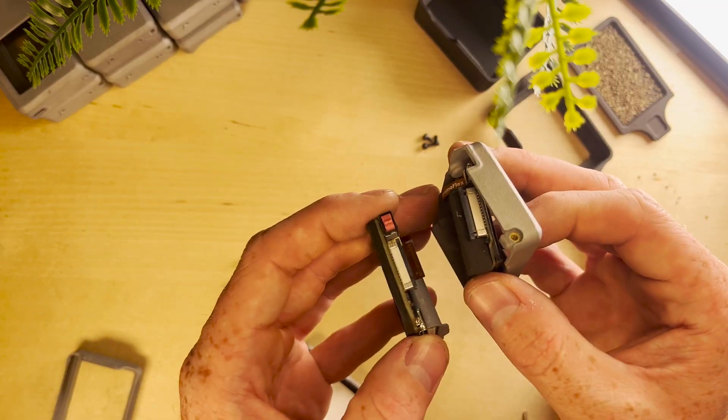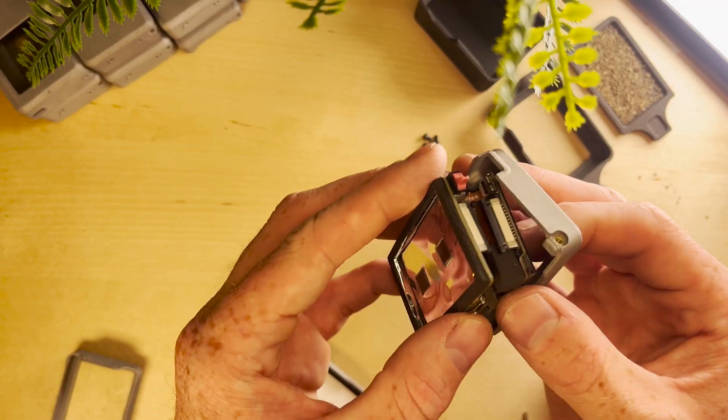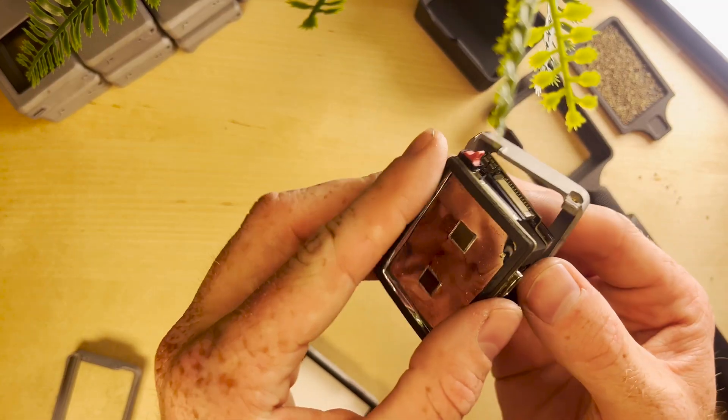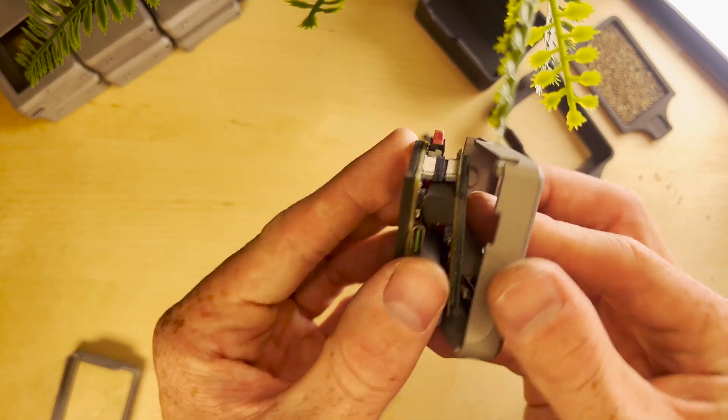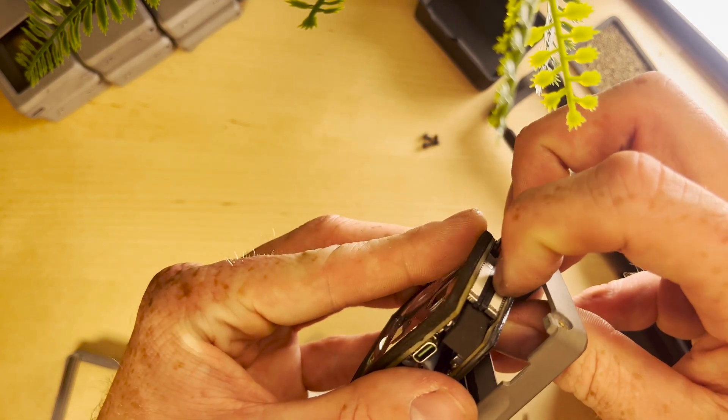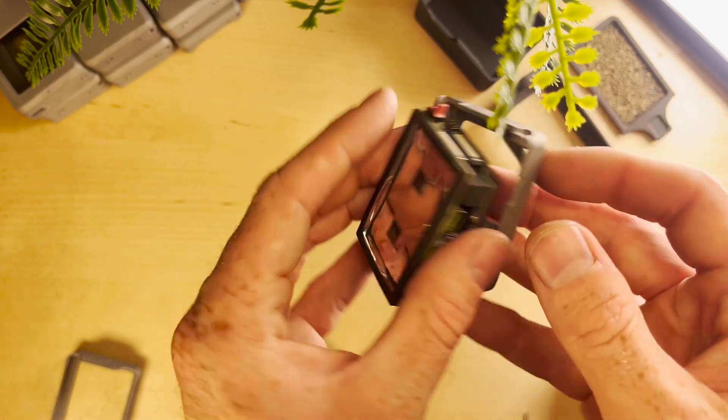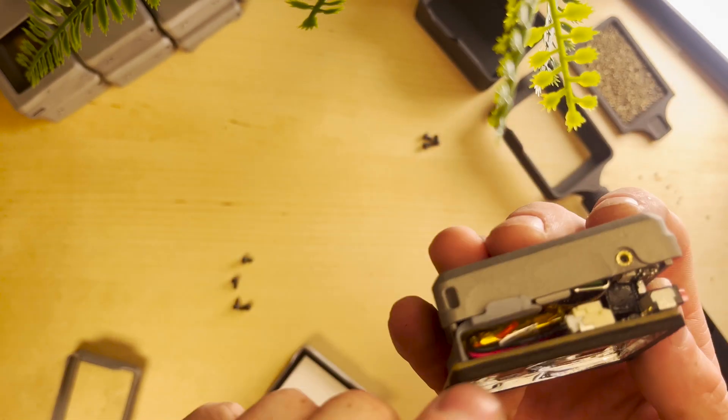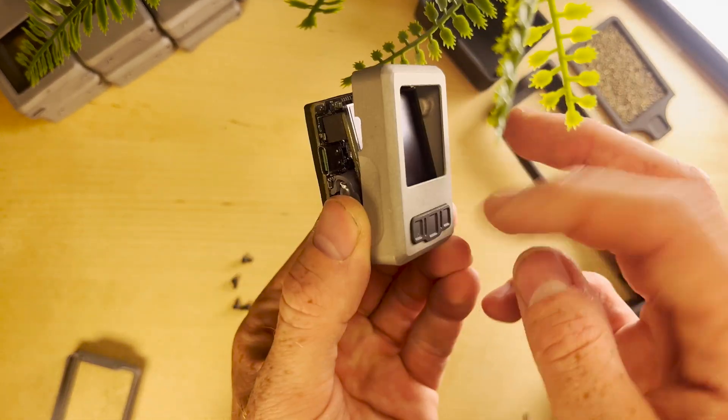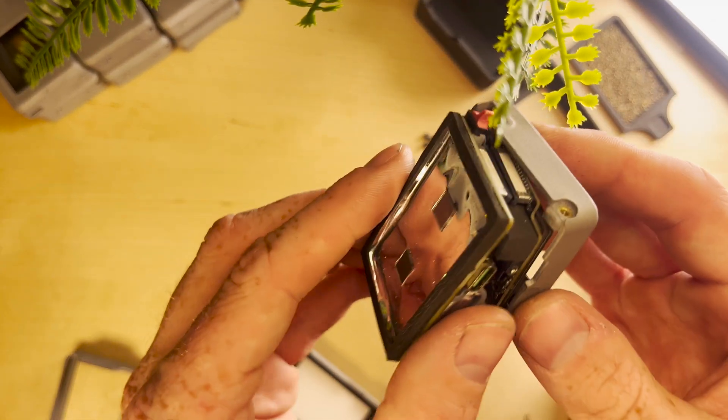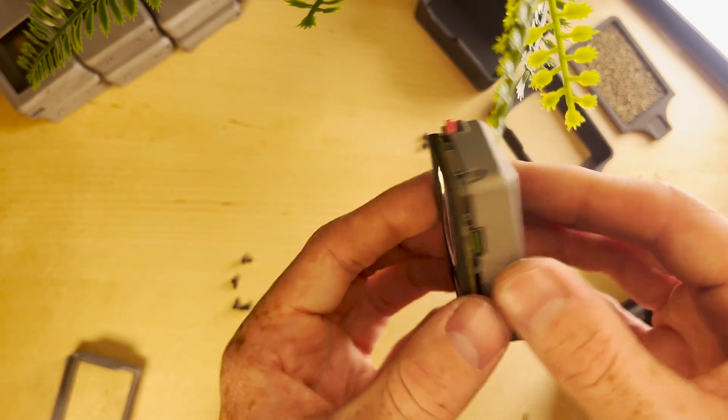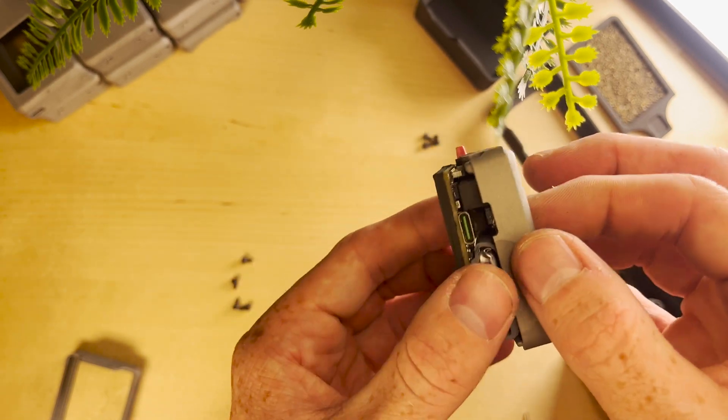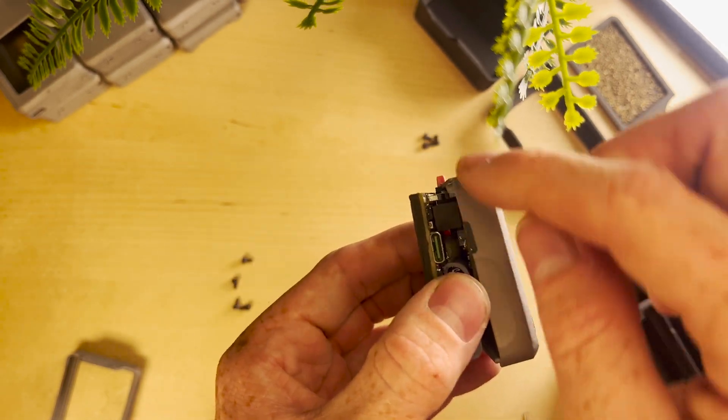There you can see that clip is open and we're going to take the main board and attach it to the display just like if you were switching out the display and we're going to hold these clips down. The reason I'm holding it like this is we have that ribbon cable that goes to the button panel here. Then we can go ahead and drop it in and you can see actually where that BGO scintillator is. It's right up there in the front of the detector.